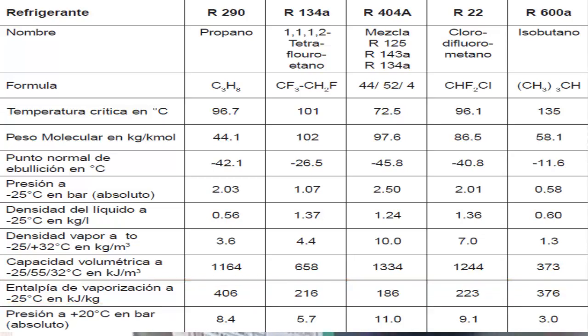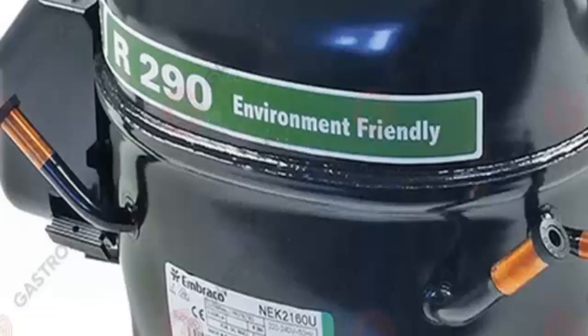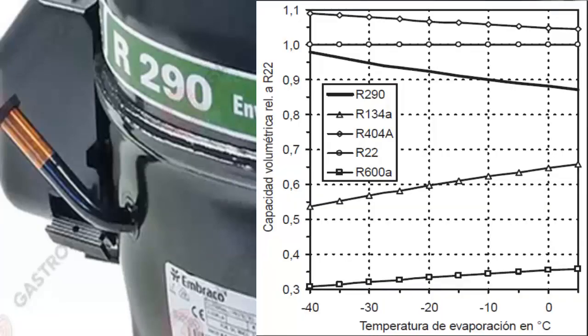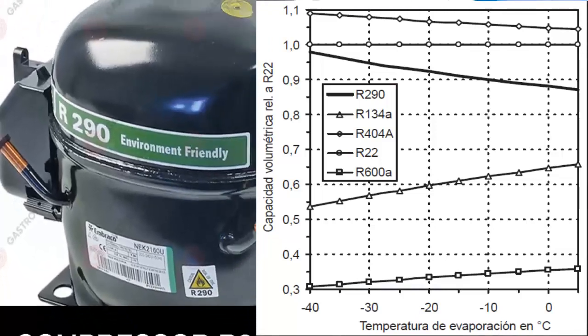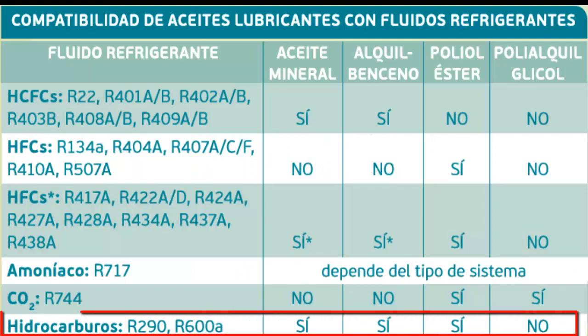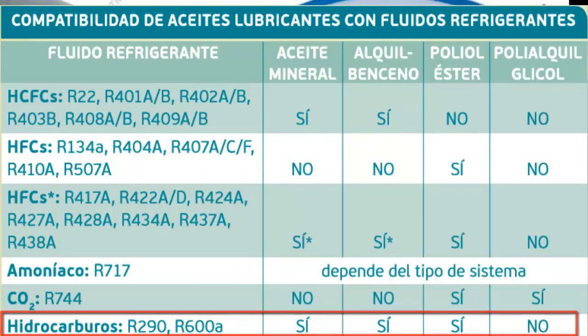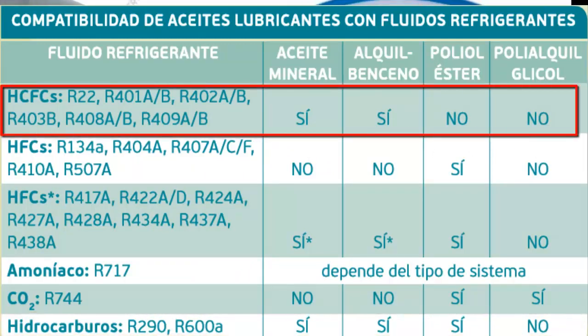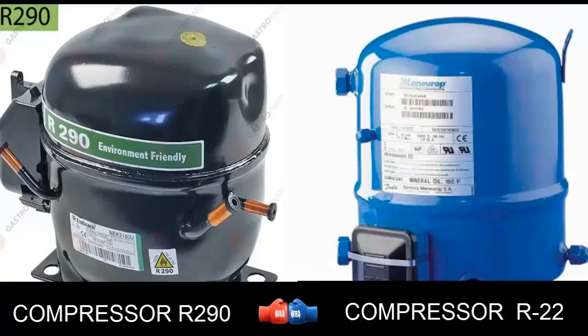The compressor with R290 has approximately 90% of the volumetric capacity of the compressor with R22. R290 is compatible with mineral oil, alkylbenzene, and polyolester oil, while R22 is mostly used with alkylbenzene and mineral oil.